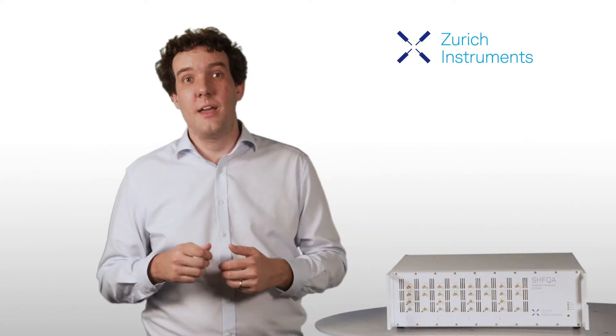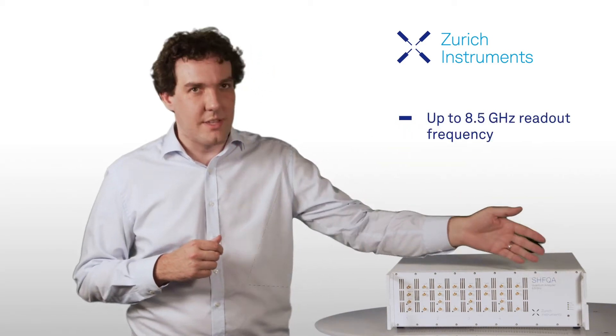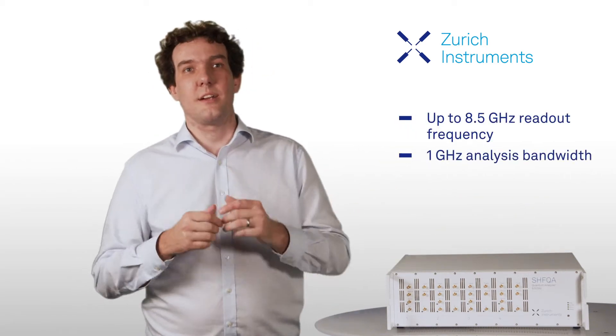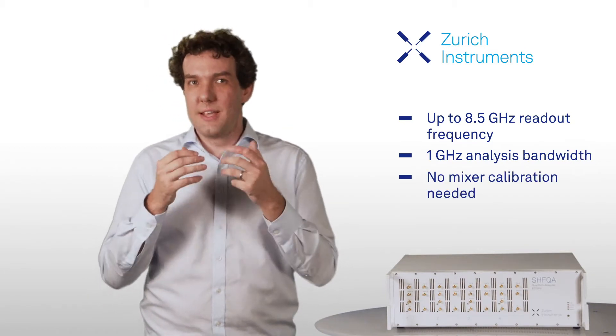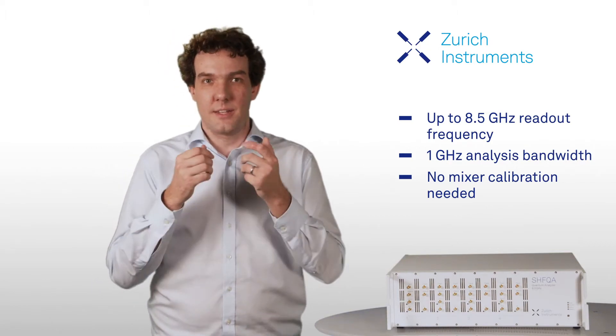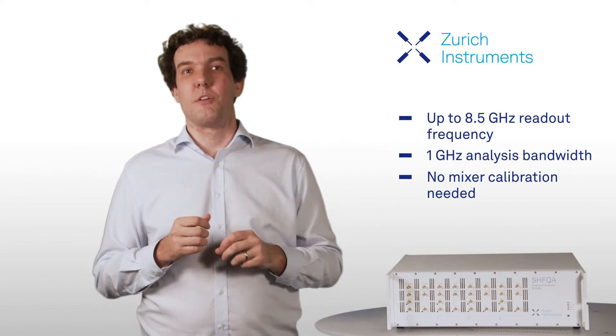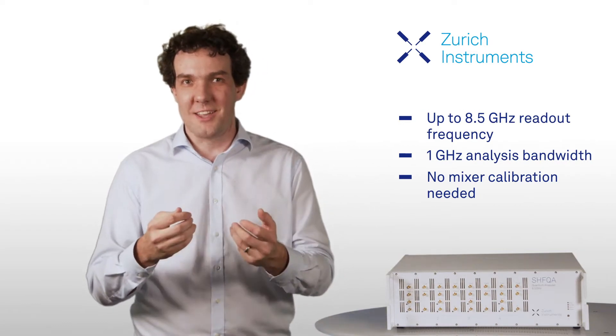The SHFQA can both generate and analyze a readout signal at up to 8.5 GHz. It offers 1 GHz of spurious-free analysis bandwidth without the need for regular calibration, thanks to its double superheterodyne frequency conversion, which ensures that the signal is clean and stable right from instrument startup. Contrast this to a setup using IQ mixers.